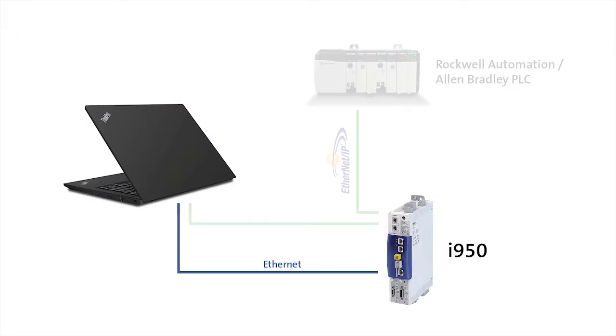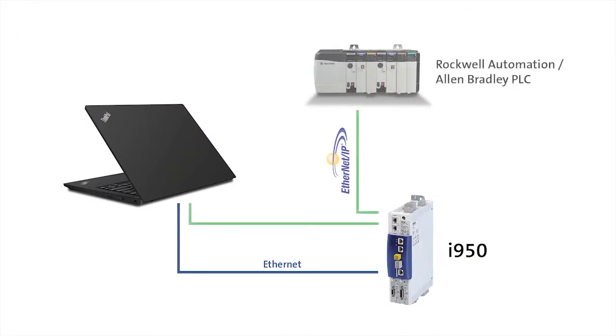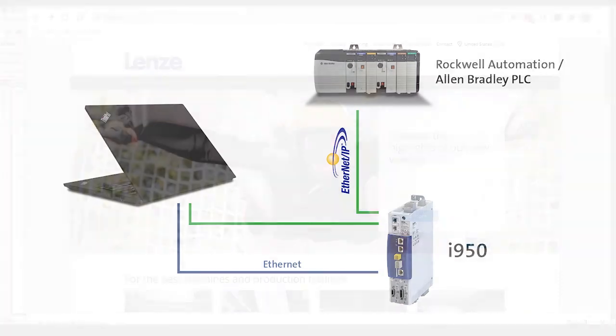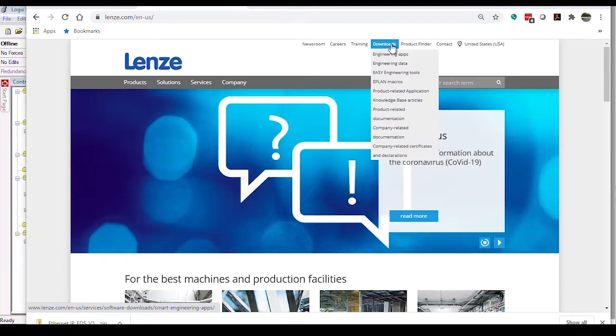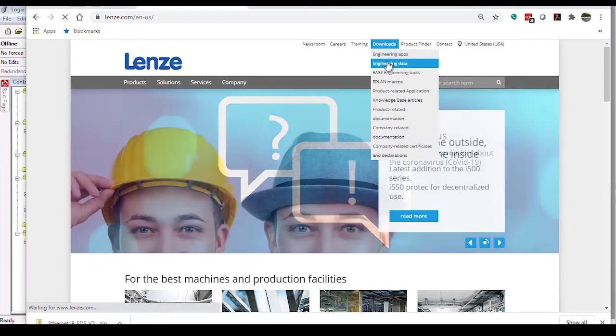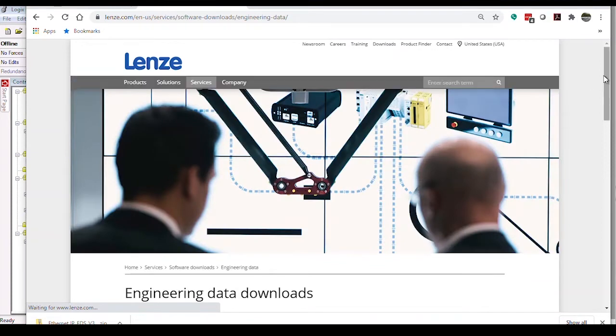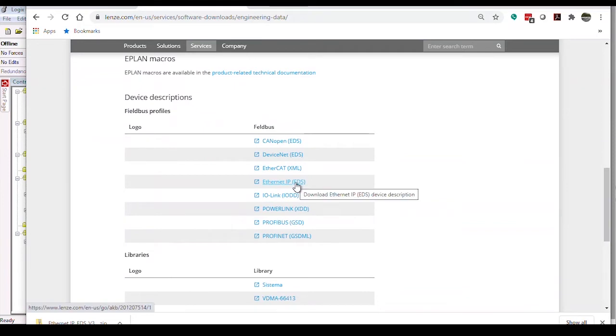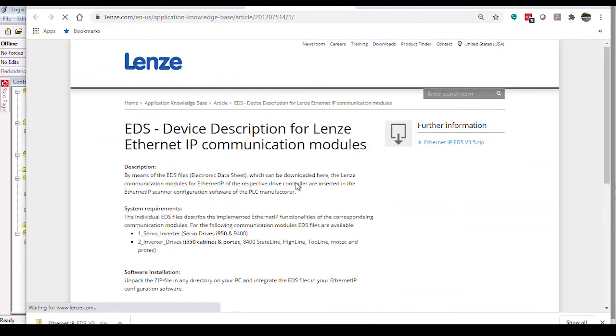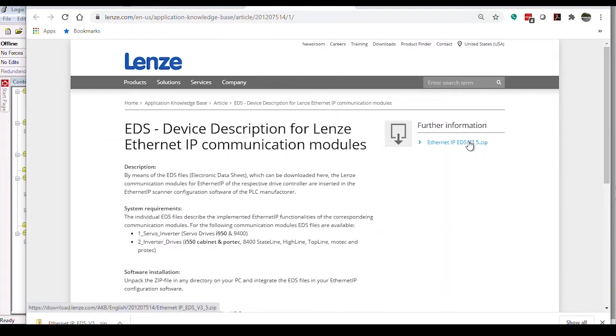Now that we have the drive set up for communication, we can begin the setup on the Rockwell and Allen Bradley side. In order to recognize the device as an i950, Rockwell programs will need something called Electronic Data Sheets, or EDS for short. You can go to our Lenze.com official website, go to the Downloads section, then click on Engineering Data. Scroll down until you see Ethernet IP EDS under the Device Description section. Download the files and save them to a location you can navigate to on your computer.